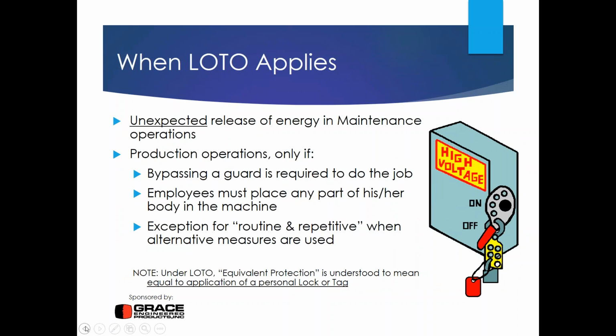Now, when lockout applies, the general rule is that for maintenance activities, it's assumed that virtually all maintenance activities will be done in a locked out, tagged out state. If you think back to the NFPA 70E, those of you that have had that training, while you're in the troubleshooting mode, it's assumed that it's okay to do some troubleshooting or voltage testing. But once you've identified what the problem is, at that point you're required to lock out, tag out.